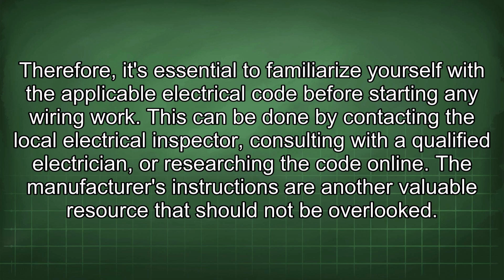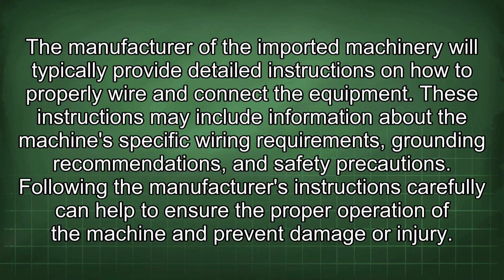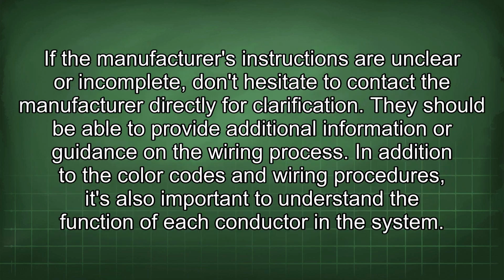The manufacturer's instructions are another valuable resource that should not be overlooked. The manufacturer of the imported machinery will typically provide detailed instructions on how to properly wire and connect the equipment. These instructions may include information about the machine-specific wiring requirements, grounding recommendations, and safety precautions. Following the manufacturer's instructions carefully can help to ensure the proper operation of the machine and prevent damage or injury. If the manufacturer's instructions are unclear or incomplete, don't hesitate to contact the manufacturer directly for clarification. They should be able to provide additional information or guidance on the wiring process.